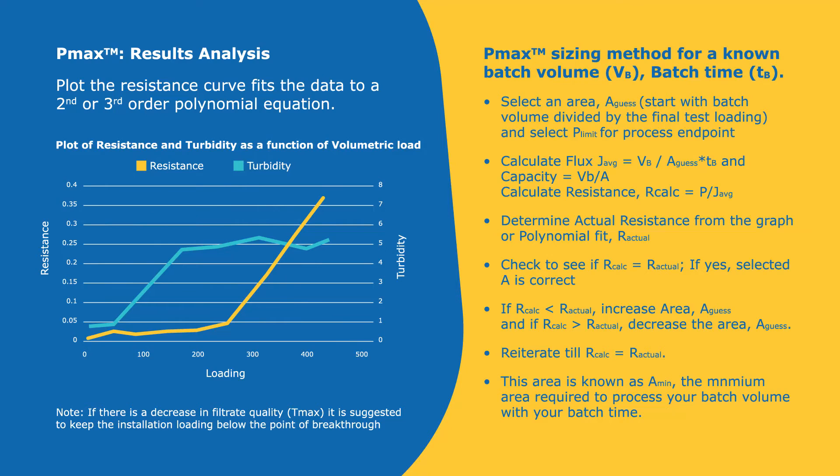Once you have your table of data, which would be time, volume, and turbidity, you're going to use your time and volume data. You're going to plot the resistance curve. So you're going to have resistance on the y-axis and a loading or capacity number on the x-axis. Resistance is in terms of pressure over flux, which is liters per meter squared per hour. And the loading or capacity on the x-axis is liters per meter squared.